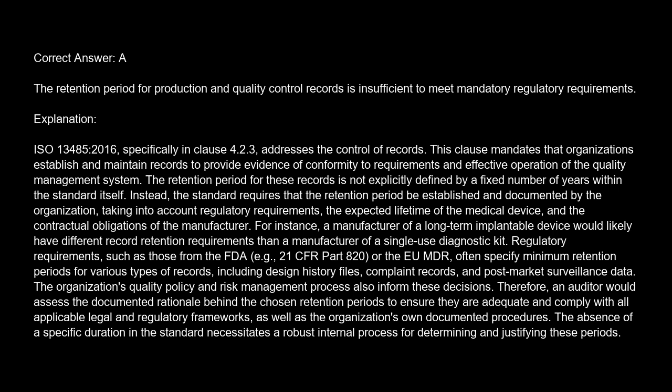This clause mandates that organizations establish and maintain records to provide evidence of conformity to requirements and effective operation of the quality management system. The retention period for these records is not explicitly defined by a fixed number of years within the standard itself. Instead, the standard requires that the retention period be established and documented by the organization, taking into account regulatory requirements, the expected lifetime of the medical device, and the contractual obligations of the manufacturer.